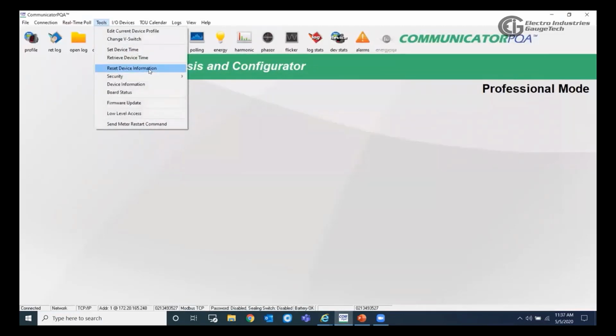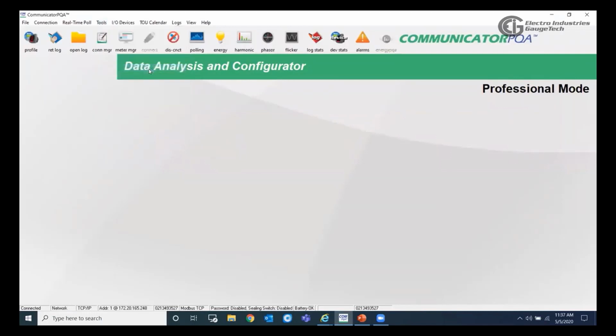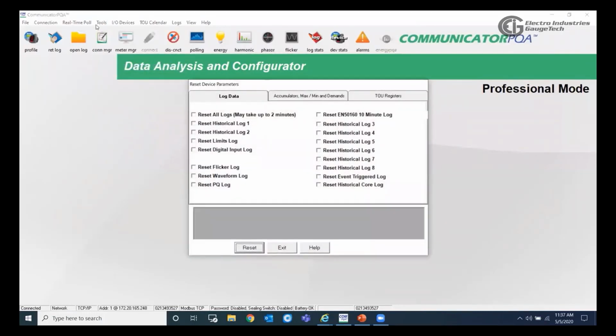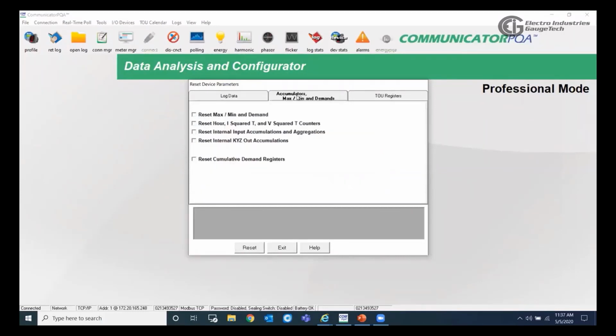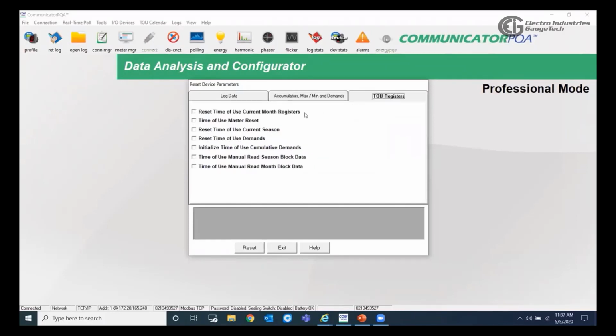We can also reset the energy accumulators and some other items from here, reset device information. So we have the option to reset all the logs, or we can choose one or two, or whichever log we want to reset. And we also have the option to reset the energy accumulators from here, reset the I2T and V2T counters, the max, minimum, and demand, and the time of use registers also. So we just have to check the boxes here and hit reset.